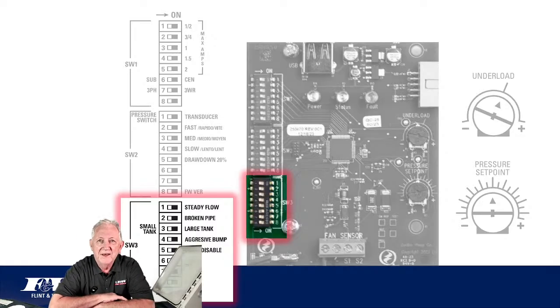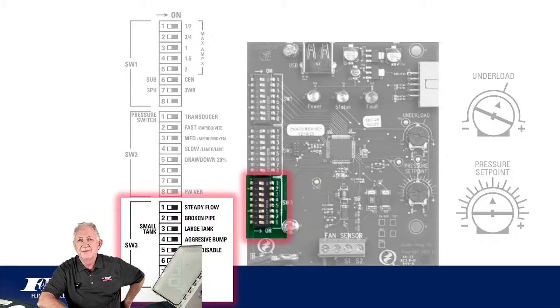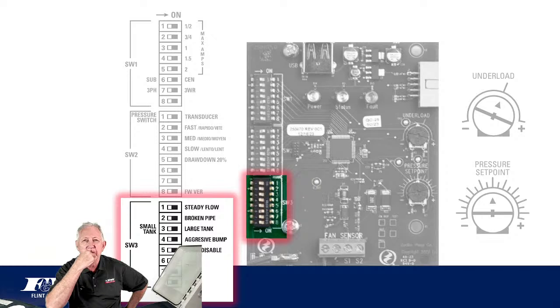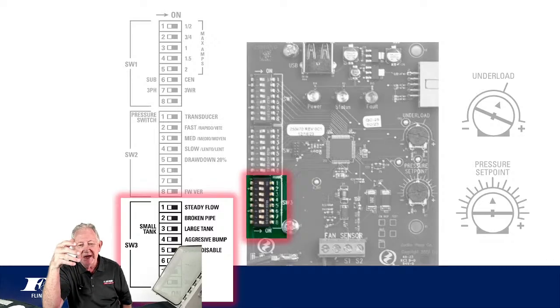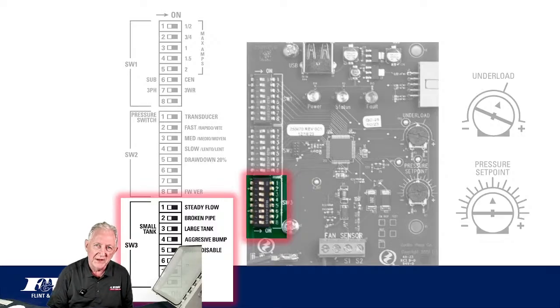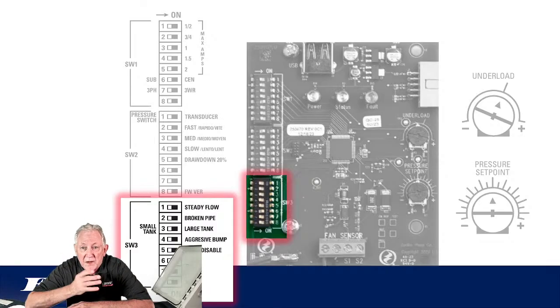So this next slide gets down to this catch-all at the bottom. Again, most of the things down here would be needed only if we want to fine-tune or tweak this thing. You've got a broken pipe feature that you can turn on and off. As far as protection goes, if you're installing this drive and upgrading a conventional system that already has a pressure tank installed, maybe a 40-gallon pressure tank or whatever, you can keep that tank and still make this drive operate.